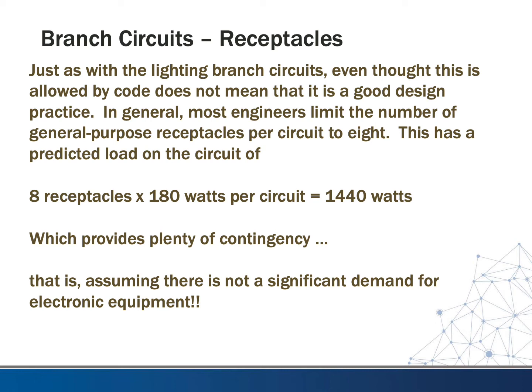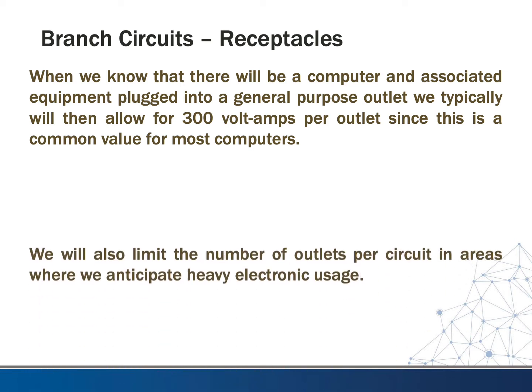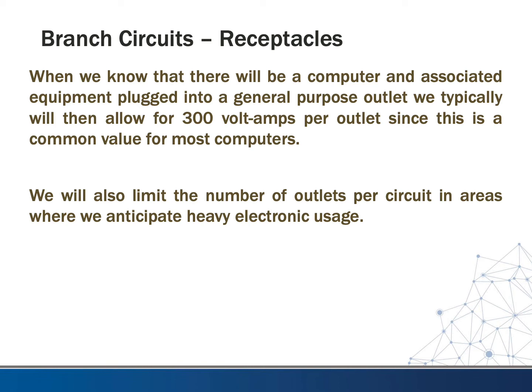If you're in a place with heavy electronics, you might want to modify this. For example, if we have a lot of offices in a row, we might put one circuit per office — usually four outlets — so it's four per circuit. When we know that there will be a computer and associated equipment plugged in, we typically allow at least 300 watts per outlet, since most power supplies on desktop computers are around 300 watts. We also limit outlets per circuit in areas with heavy electronic usage.